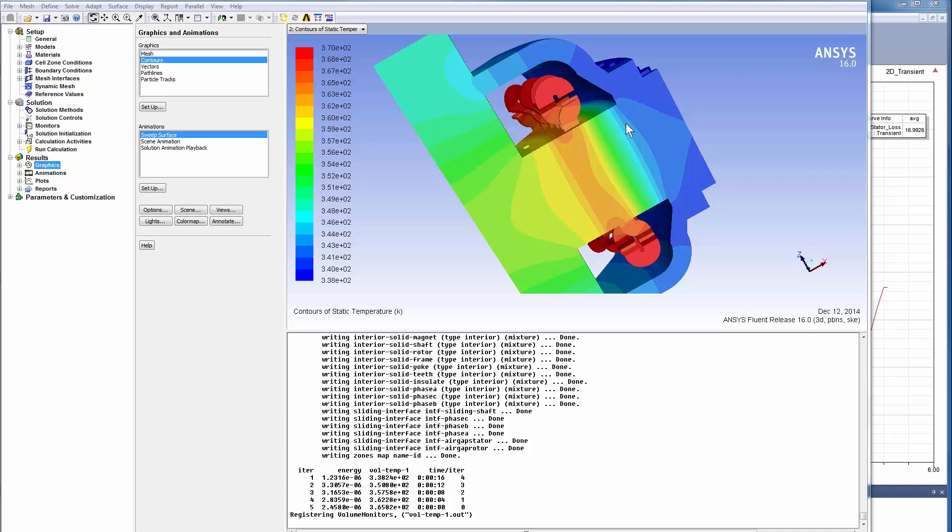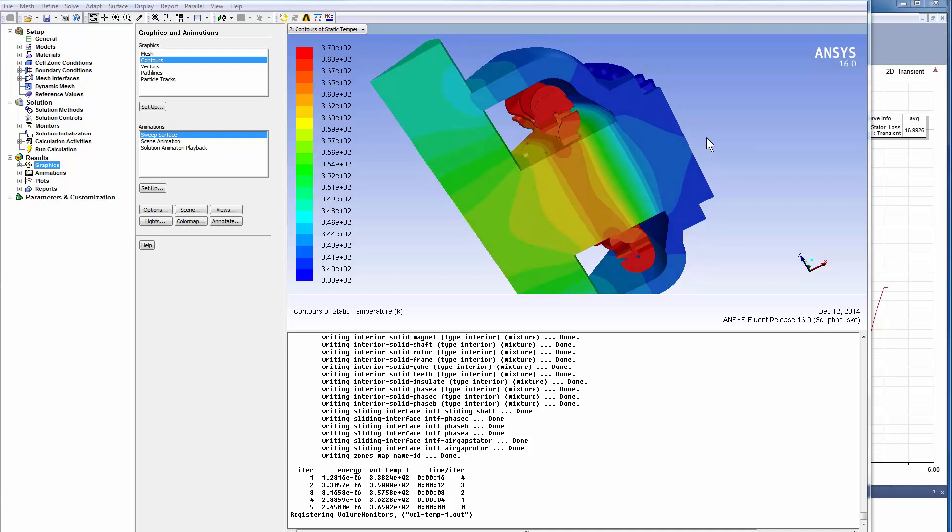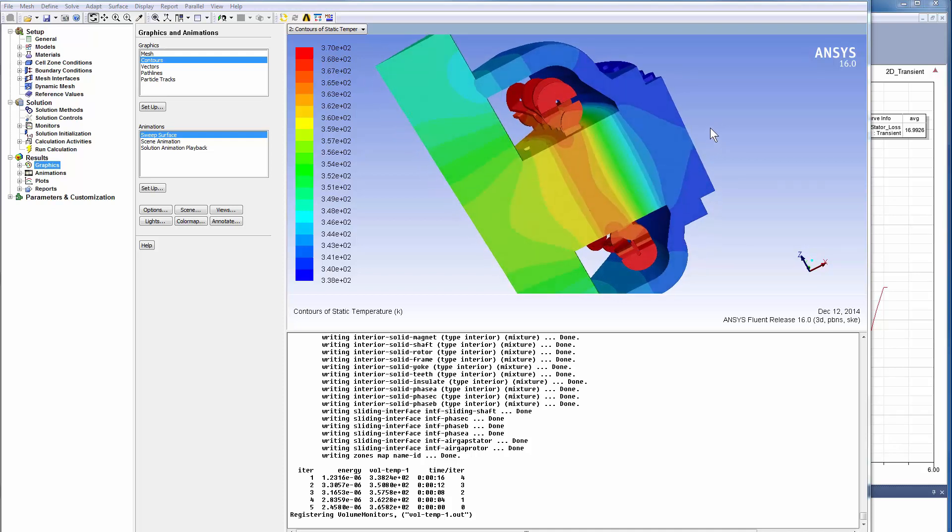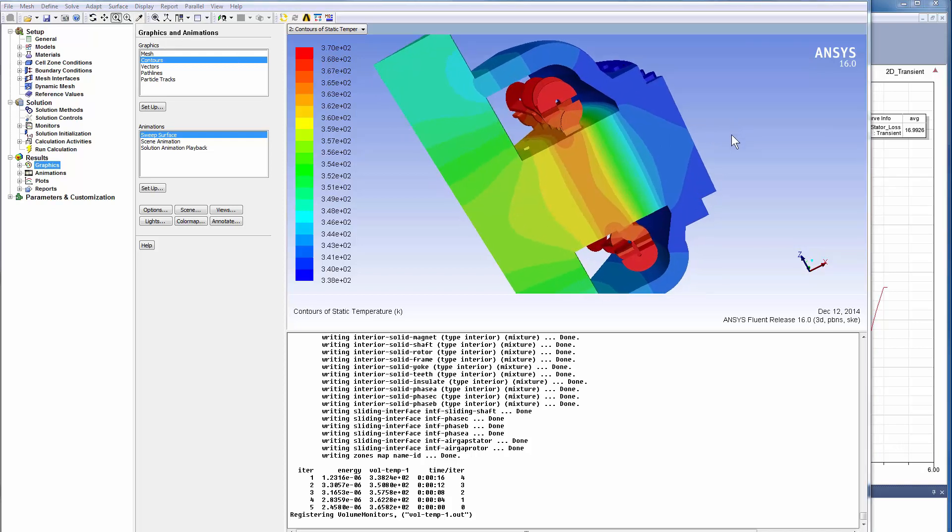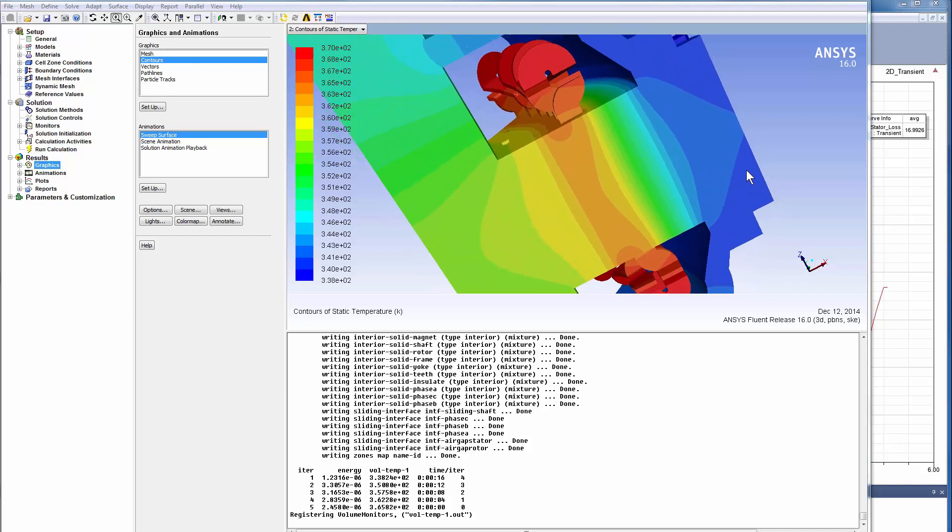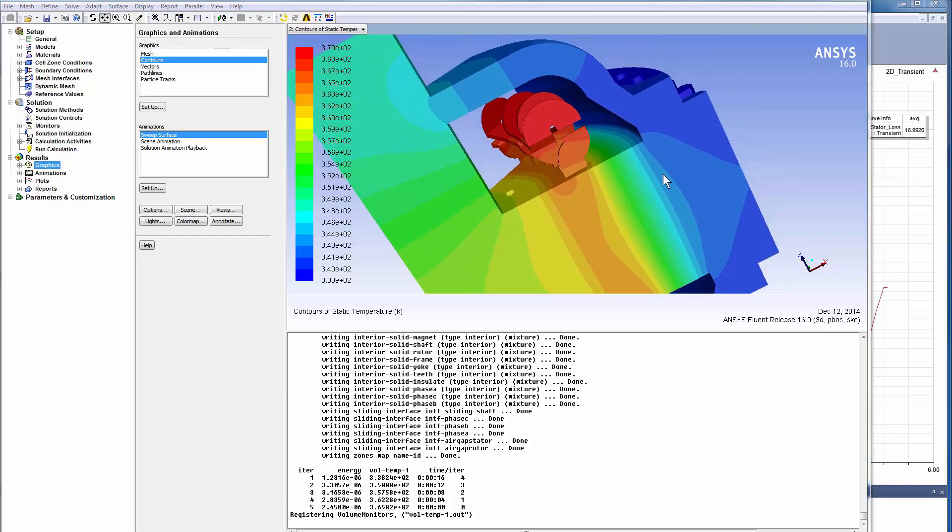When this temperature distribution is passed back to Maxwell, all conductive materials are changed based on local temperature. This will affect the magnetic field distribution and also power loss. The designer will see and learn what is needed to do to reduce any hot spots. Such two-way coupling helps engineers understand how to properly design and improve a complex cooling system.